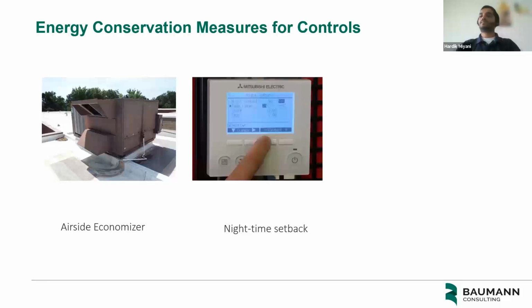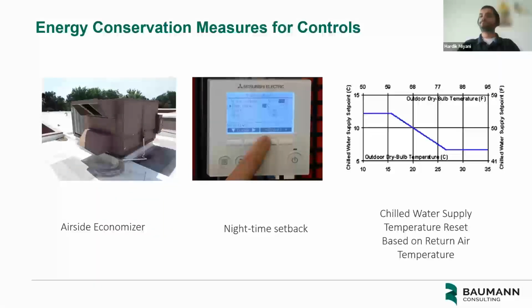Next is the nighttime setback. This is something that I explained a few slides ago. Whenever the building is in unoccupied mode, you can change the set points from occupied to unoccupied. So, for example, instead of keeping your set points at 70 for heating and 72 for cooling, you can bring it down to like 60 for heating and 80 for cooling. So this will help you to save energy.